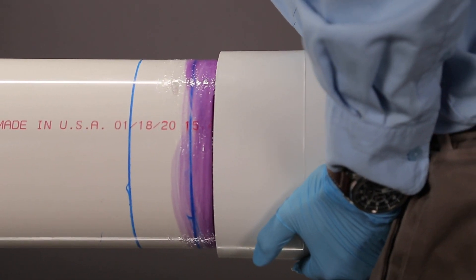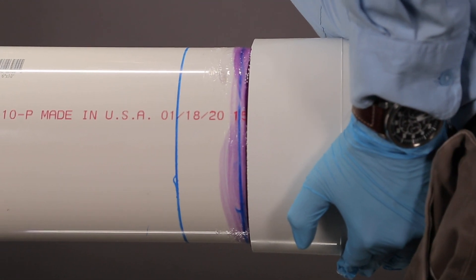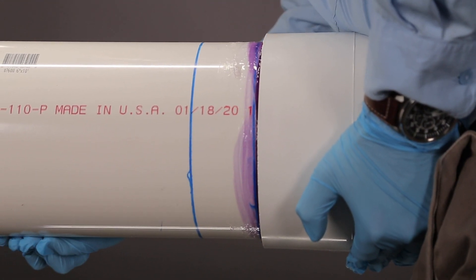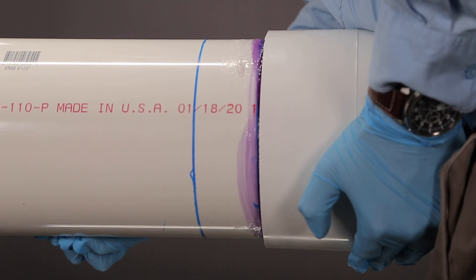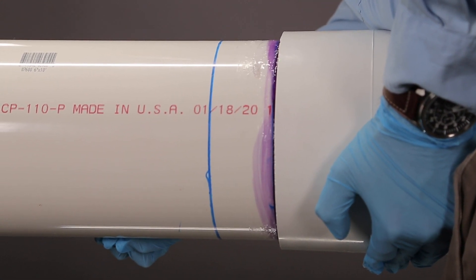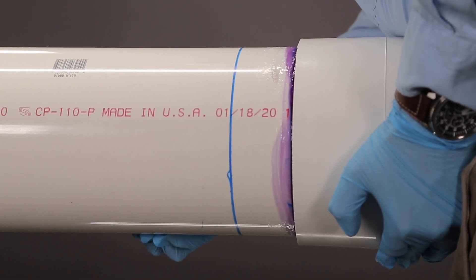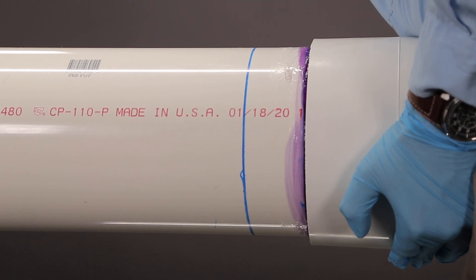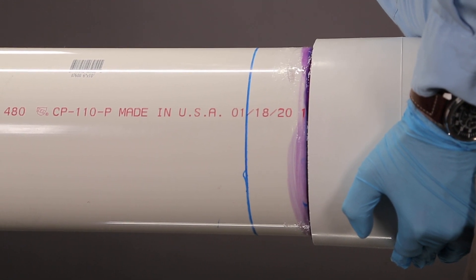Quickly assemble pipe and fittings while the cement is still fluid. If it hardens, you have to cut the pipe and start over with a new fitting. It is very important that the pipe is fully inserted into the fitting. Large diameter pipe is heavy and can be resistant to insertion. We recommend that you use a pulling tool.